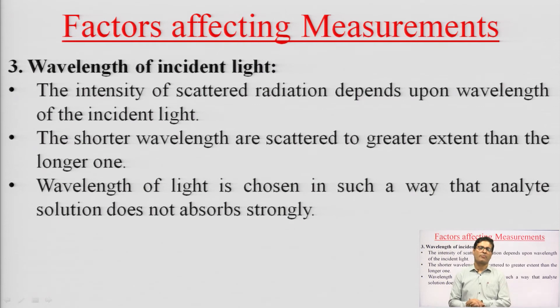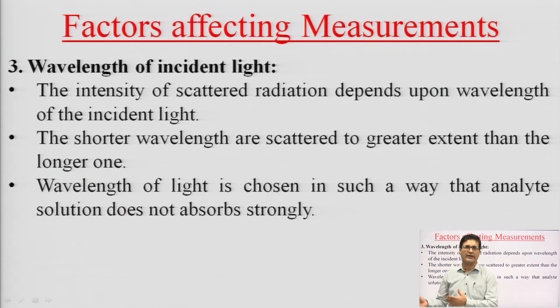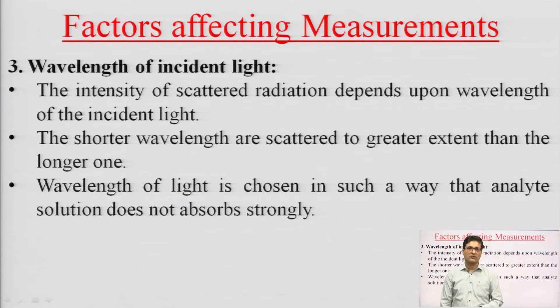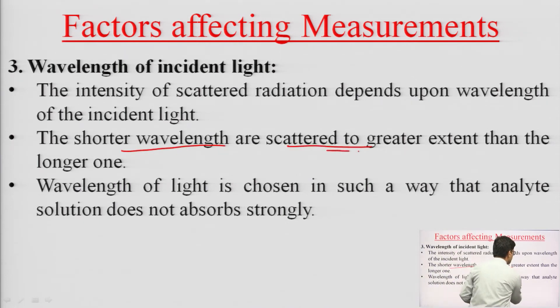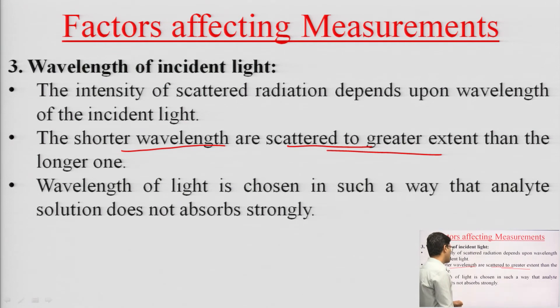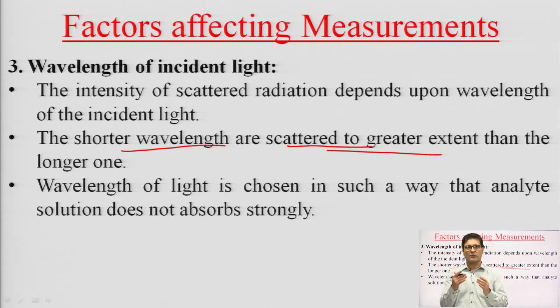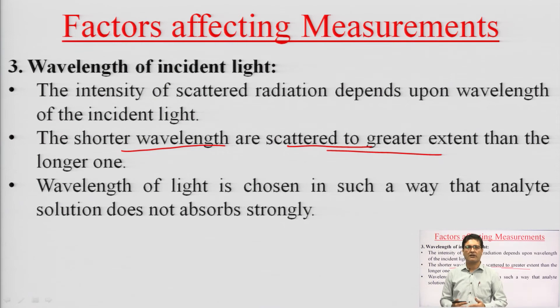The third factor is the wavelength of incident light. As seen in Rayleigh's law, scattering is inversely proportional to the fourth power of wavelength — the smaller the wavelength, the greater the scattering. The intensity of scattered radiation depends on the wavelength of incident light, so shorter wavelengths are scattered more than longer wavelengths. Wavelength of light is generally chosen so that the analyte solution does not absorb strongly — absorption should be minimum and scattering should be more when performing nephelometric determinations.